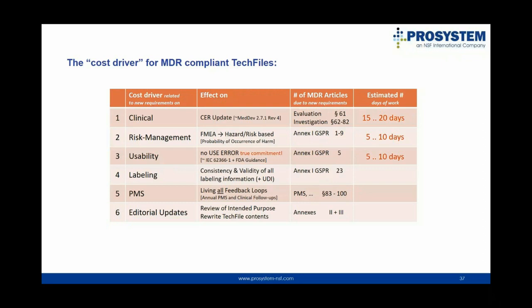The usability piece is a stepchild of the family. In the last 10 years, many manufacturers have no very adequate usability files. There is no grandfathering ruling in the MDR, so we start from scratch. A new complete usability engineering file needs to be in the MDR technical documentation. Here, our estimates are only the gap. If somebody would completely comply with MDD today, what is the delta to go to MDR? But if you have less than that, the work is even more intensive.